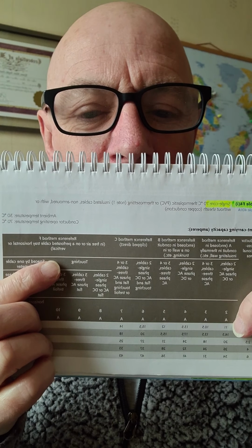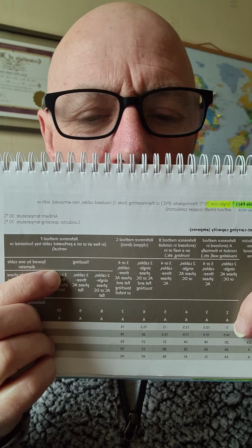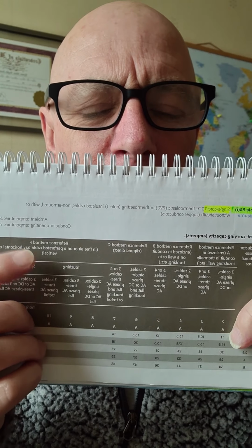One update that there's been is this section over here, which is talking about cables that are separated by more than one diameter or so. So that's a bit different in there. Chances are most of the time you won't be using that, because you're more likely to be using cable tray for armoured cables, and this doesn't cover that. So F4.1 is to calculate your size of cable based on the current that it can carry, and it's for single cables.